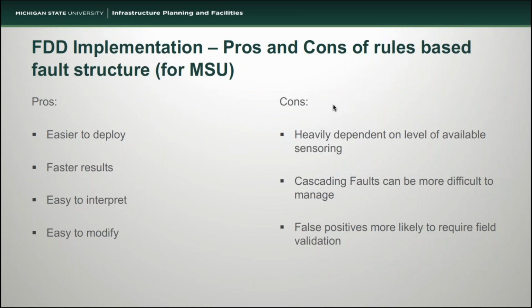So for MSU, and I'm stressing MSU because the benefits of any particular system are going to be highly dependent on the organization, what their funding structure is, and what their goals are. But for MSU, because we wanted to primarily self-perform, the pros of a rules-based fault structure for us are it was easier to deploy. You get faster results from it because you don't have to train a model before you start seeing issues. You put a rule in place, and either the air handler is breaking the rule or it's not breaking the rule. They're easier to interpret because they're laid out in a logical way. And again, it's black and white. Either it is breaking the rule or it is not breaking the rule.